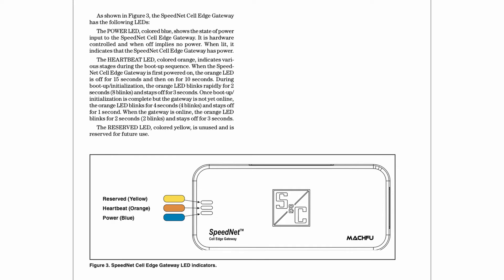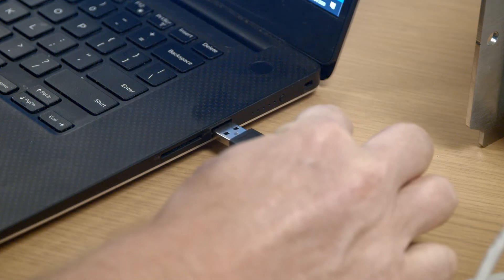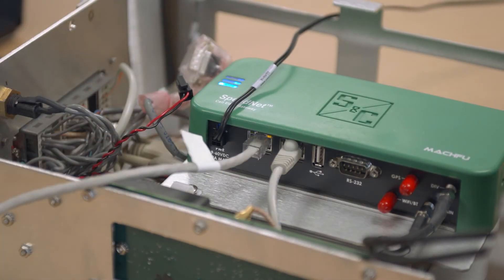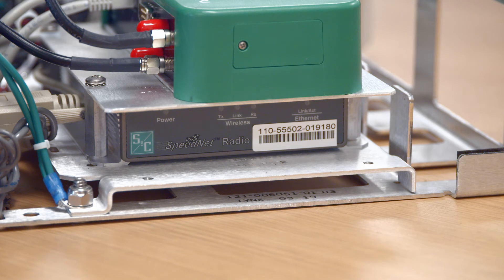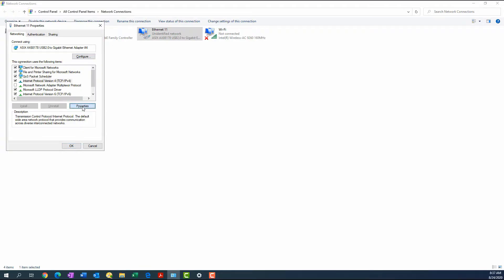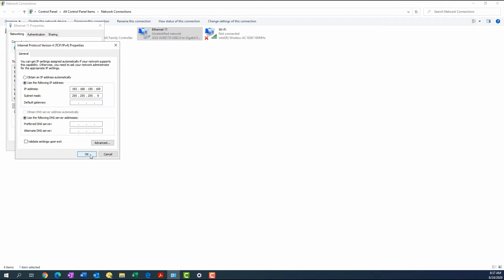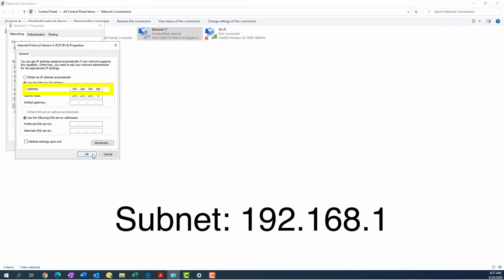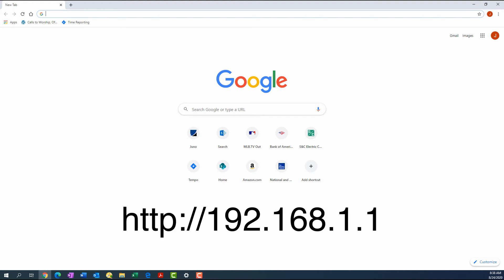Connect a PC to the Ethernet-1 port. If configuring a gateway for a system where the cellular network is used in conjunction with a Speednet radio network, this will require first removing the Ethernet cable connected to the port. The properties of the Internet Protocol Version 4 item of the PC port connected to the gateway must be configured to have an IP address on the 192.168.1 subnet. This can be done by changing the adapter settings on the PC. Once the adapter settings are correct, launch a web browser and navigate to 192.168.1.1 in the address field.